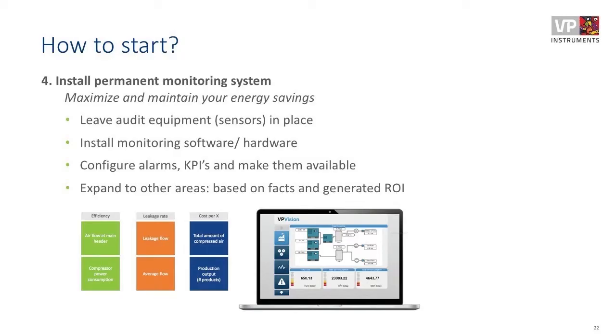The next step is to install a permanent monitoring system. Those sensors have been equipped with a local data logger, but now you can take the next step and install the permanent monitoring system, which can be VP Vision. Basically, this VP Vision software will enable you to keep track of the critical performance indicators. It will also alarm when things go out of bounds, and it will display all the data in a very easy, understandable way. So it can become available, for example, on a large screen in the maintenance department. The reports can be sent automatically to the financial department or to an energy manager. The monitoring system really becomes a tool for all those people involved to help them establish the energy savings.